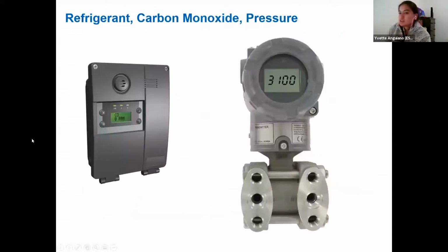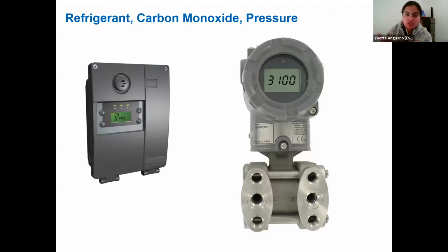So to continue on the conversation of sensors, we've also got various gas measuring devices for refrigerant leaks, which can be in electrical rooms, or carbon monoxide and carbon dioxide sensing, which can be used in garages, labs, educational spaces, or conference rooms, and many other locations. The readings of these devices can then trigger the opening of dampers in the space, or the turning on of exhaust and supply fans. Lastly, we've also got pressure sensors, which you'd want to use for water or air side systems, and can be used as a set point to control your pumps or your fan motor speeds. And that was, again, a breadth of the various types of sensors that you could possibly use in your systems.